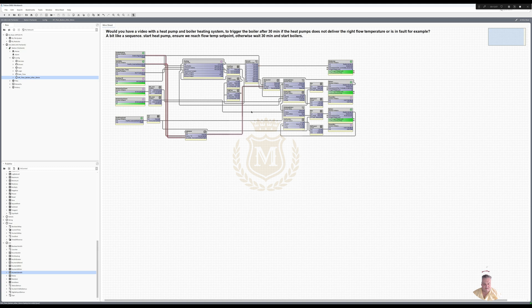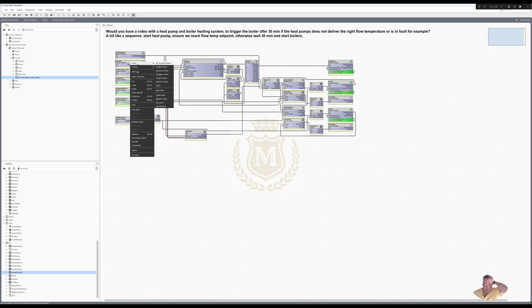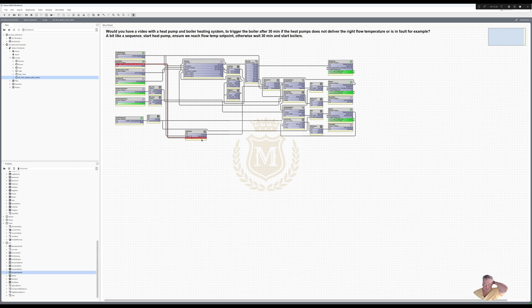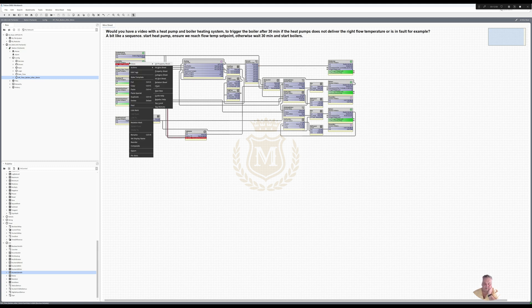So now we've got the safety tied into the boilers only — we never put the boilers on if we've got a gas problem. Let's take our gas problem and have a gas emergency active. It's fail-safe so emergency inactive — that's false. The heat pump is still working, but we'd never enable the boilers when that gets to true, because we've got a problem with the gas. Let's put that back to normal.